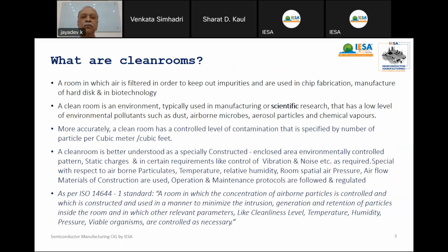Then let us understand what clean rooms are. The first two lines are available on the website: a room in which air is filtered in order to keep impurities out. A clean room is an environment typically used in manufacturing or scientific research that has a low level of environmental pollutants such as dust, airborne microbes, aerosol particles, etc. But more accurately, a clean room has a controlled level of contamination that is specified by the number of particles per cubic foot or cubic meter. In this sense, so many particles in one cubic foot, and the size. That is how we define a clean room.